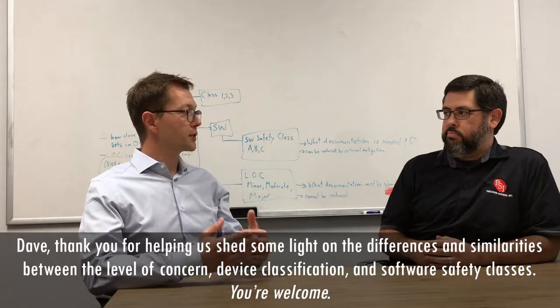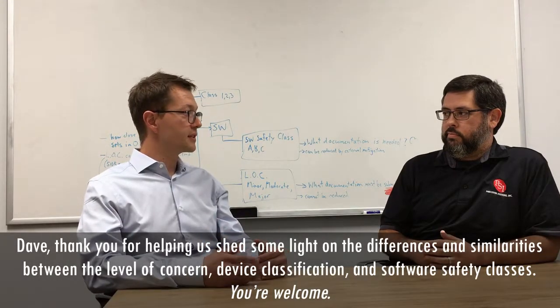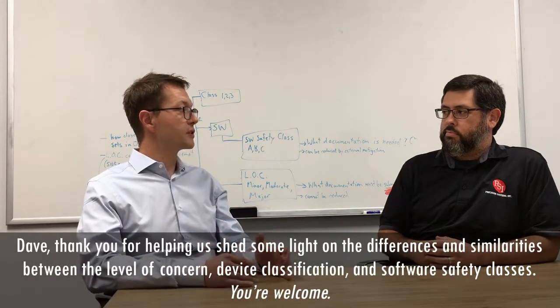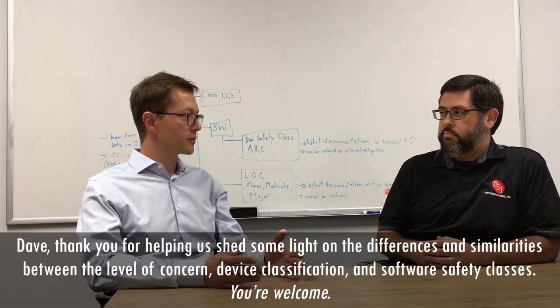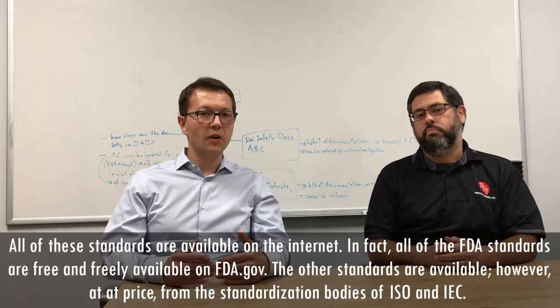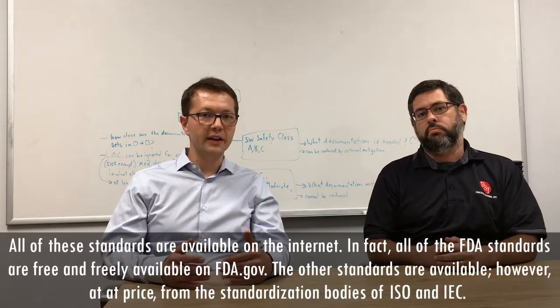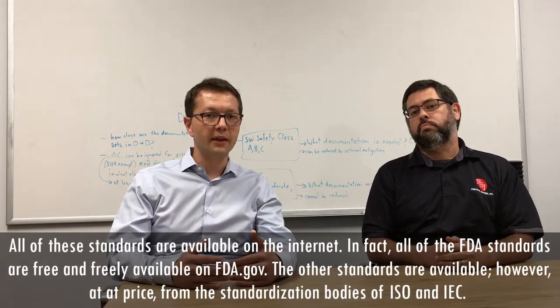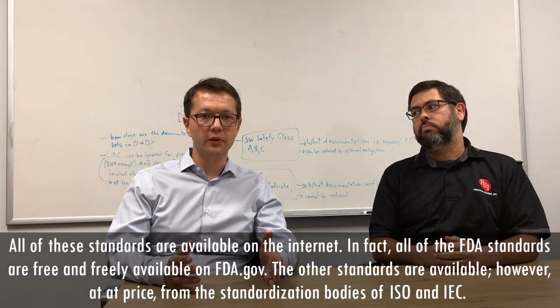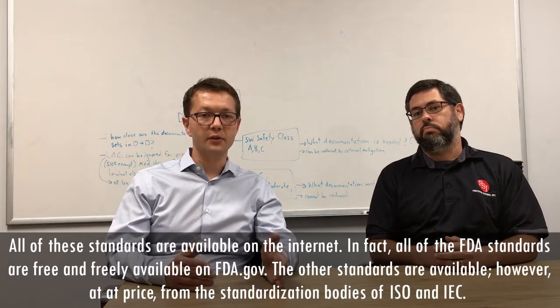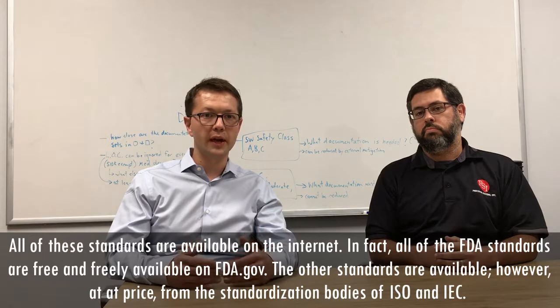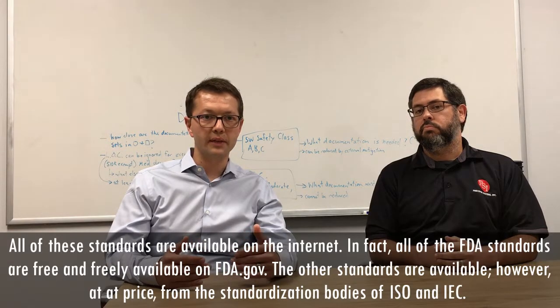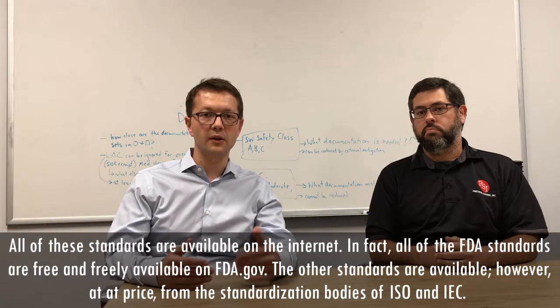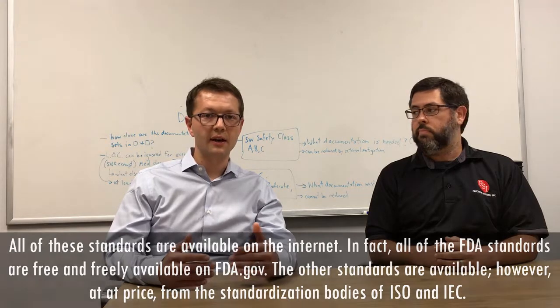So Dave, thank you for helping us shed a little bit of light on the differences and similarities between level of concern and device classification and software safety classes. You're welcome. So all of these standards are available on the internet. In fact, all the FDA standards are free and freely available on fda.gov. The other standards are available, however, at a price from the standardization bodies of ISO and IEC.